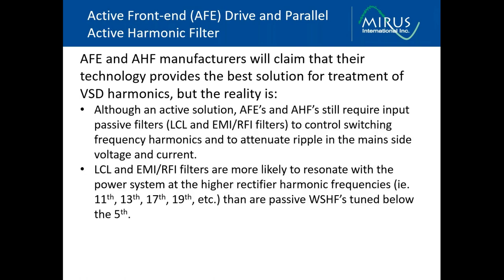Another item to highlight is that many people have indicated to me that they prefer active solutions because they don't trust passive approaches. What I tell them in response is that if you don't like passive solutions, then you shouldn't use active solutions either, because every active solution must have a passive filter in order to address the IGBT switching frequencies. Known as an LCL filter, these filters actually are more susceptible to power system resonance issues than a properly designed filter for a 6-pulse VFD. These are typically going to be tuned at much higher frequencies. When you add the impedance of the power system, it will shift the resonance frequency of the LCL filter with the power system and could shift it to predominant harmonics that are on the power system.